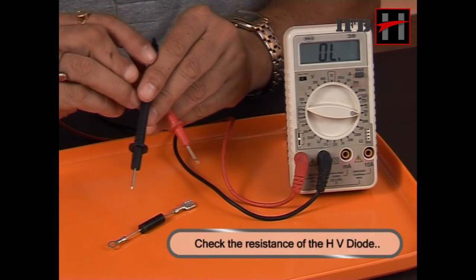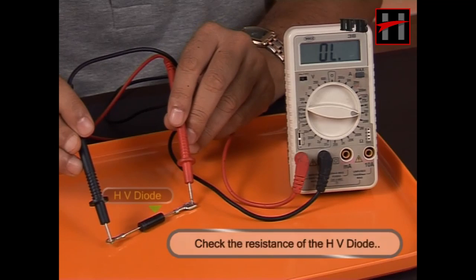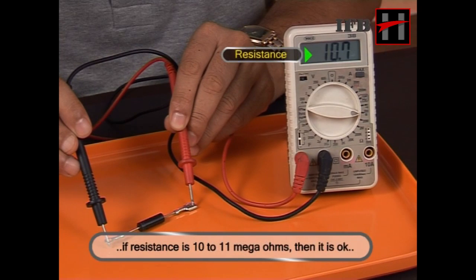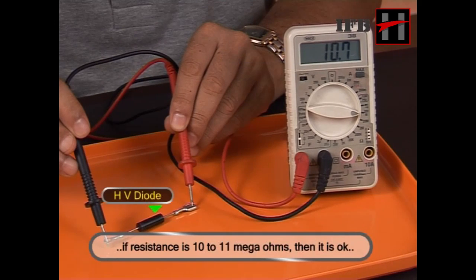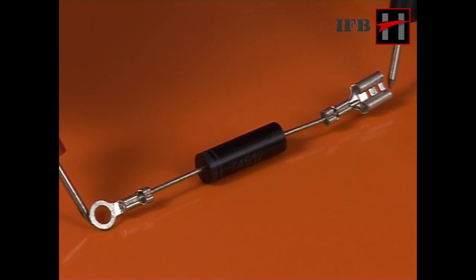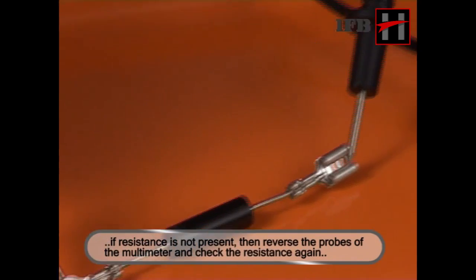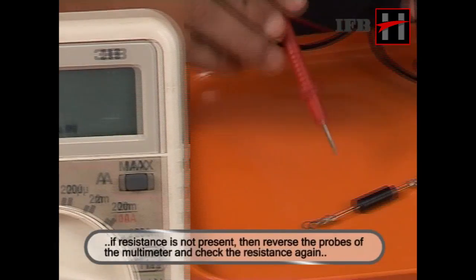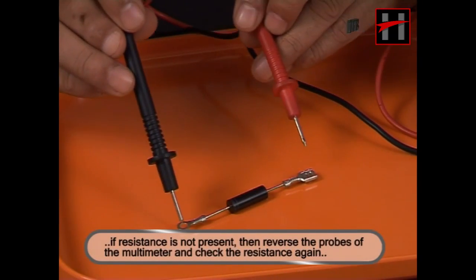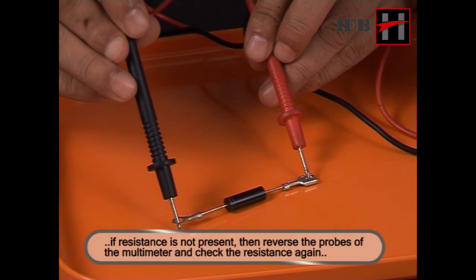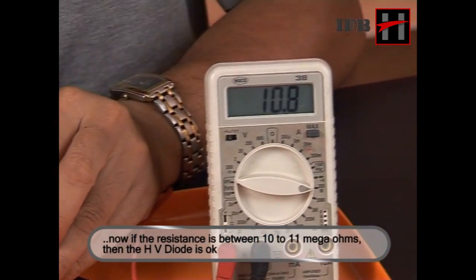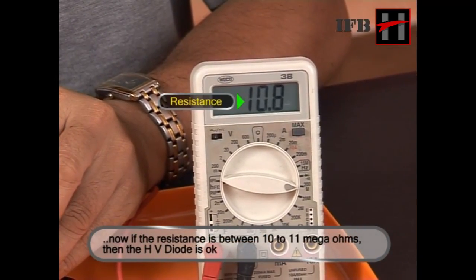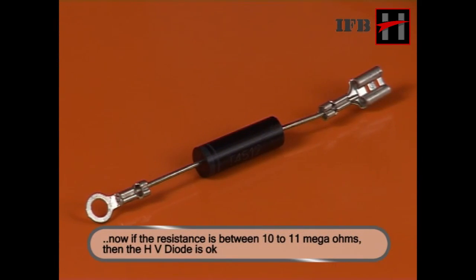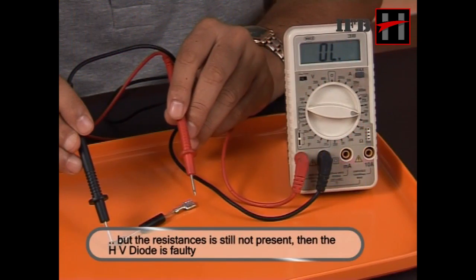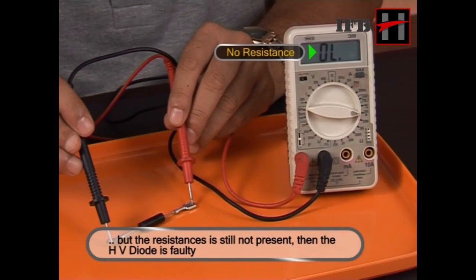Check the resistance of the high voltage diode or the HV diode. If resistance is between 10 to 11 mega ohms, then the HV diode is okay. But if resistance is not present, then reverse the probes of the multimeter and check the resistance again. Now, if the resistance is between 10 to 11 mega ohms, then the HV diode is okay. But if the resistance is still not present, then HV diode is faulty.